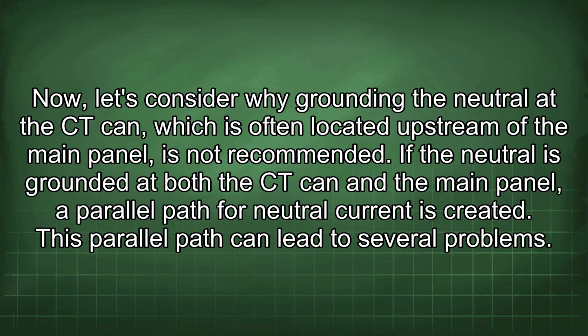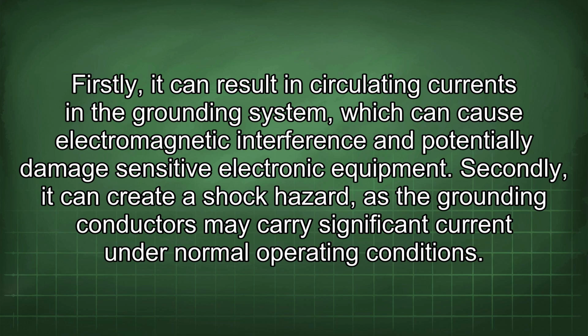Now, let's consider why grounding the neutral at the CT can, which is often located upstream of the main panel, is not recommended. If the neutral is grounded at both the CT can and the main panel, a parallel path for neutral current is created. This parallel path can lead to several problems. Firstly, it can result in circulating currents in the grounding system, which can cause electromagnetic interference and potentially damage sensitive electronic equipment. Secondly, it can create a shock hazard, as the grounding conductors may carry significant current under normal operating conditions.